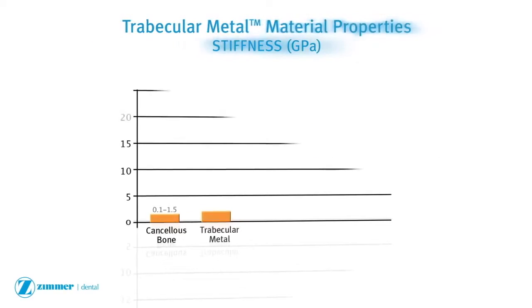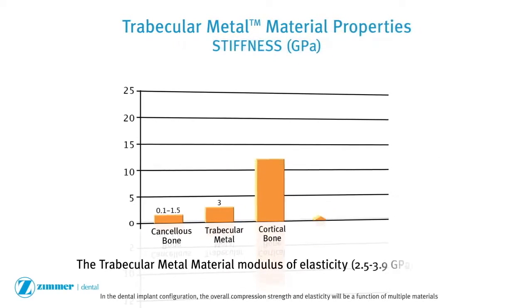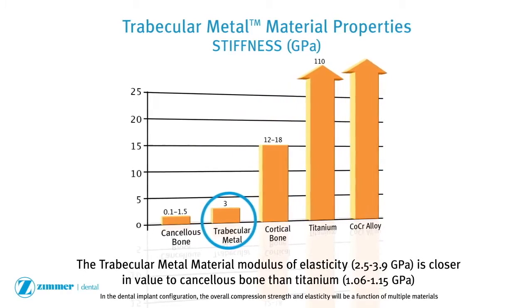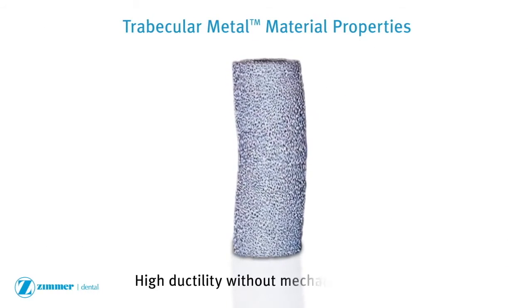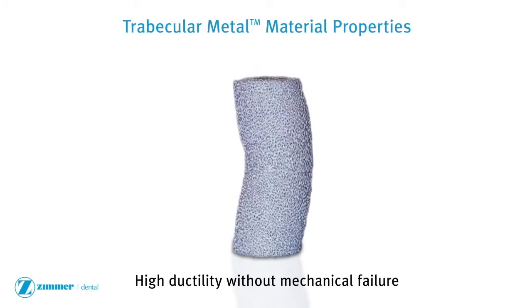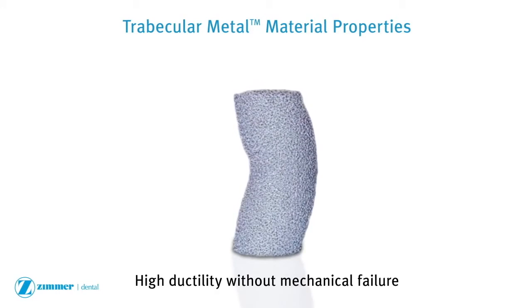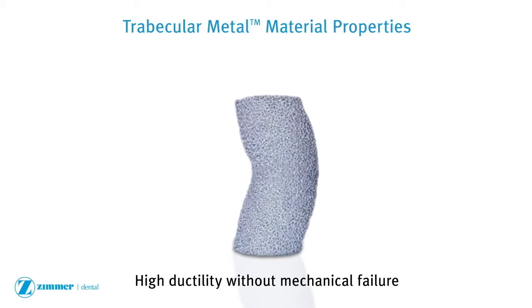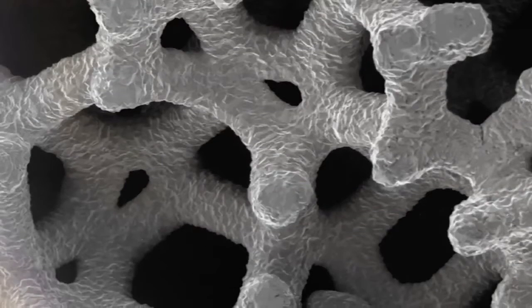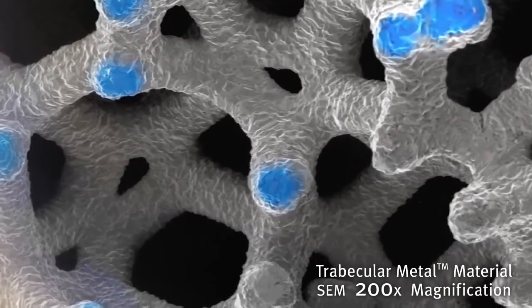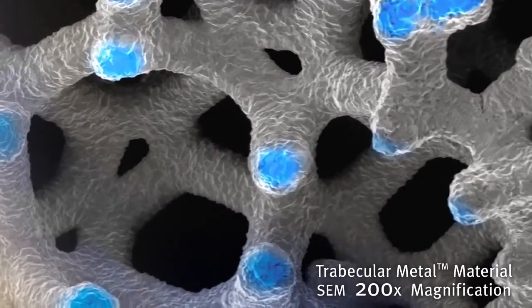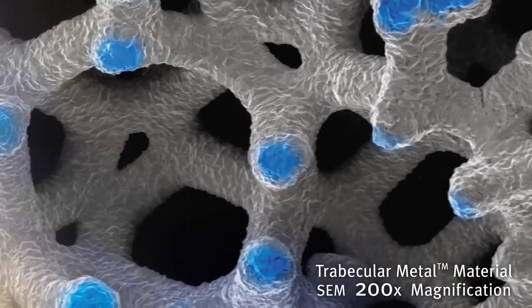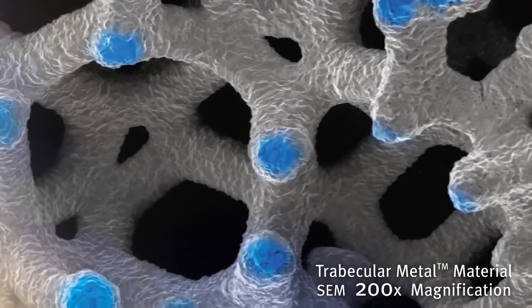Trabecular metal material has a low modulus of elasticity similar to cancellous bone. In compression testing, trabecular metal material exhibits high ductility without mechanical failure. Trabecular metal material has been demonstrated to contribute to the primary stability of the implant based on in vitro insertion torque testing.